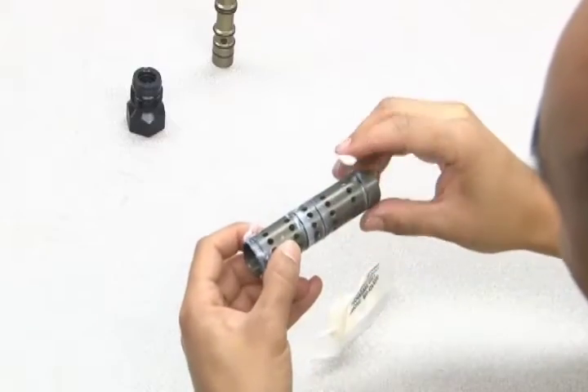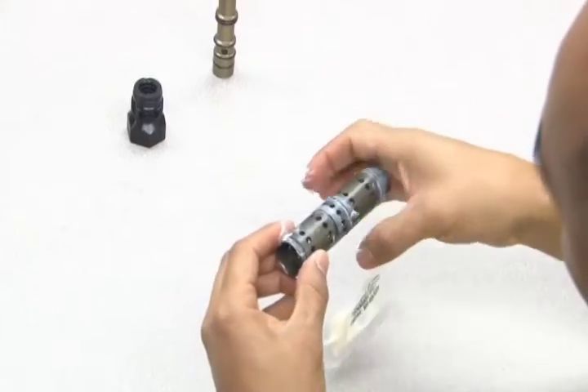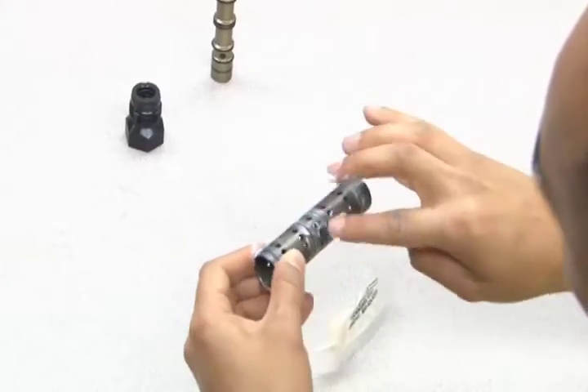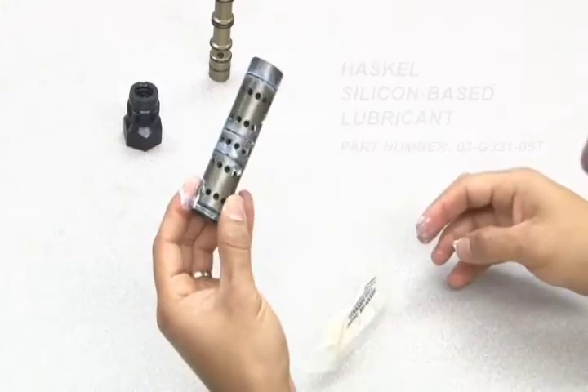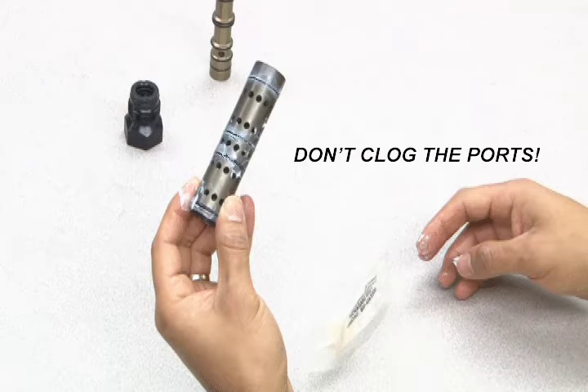One of the most common causes of continuous cycling is lack of proper lubrication on the O-rings. As a first step in troubleshooting any continuous cycling problem, apply a generous amount of Haskel silicone-based lubricant to all O-rings in the affected area, making sure not to clog any of the ports.